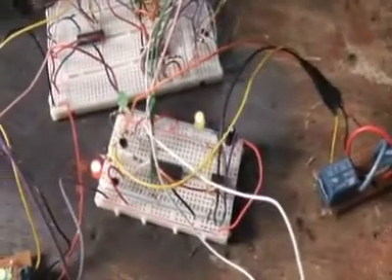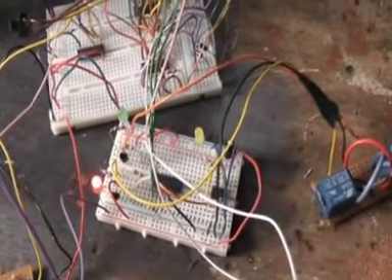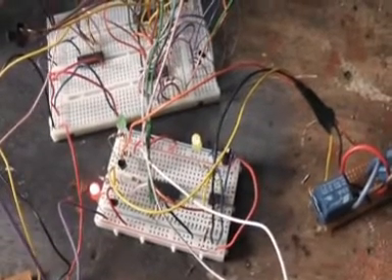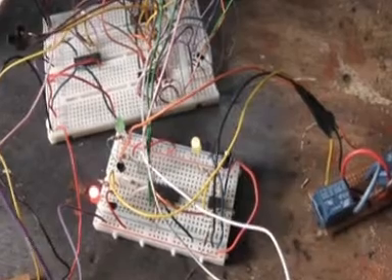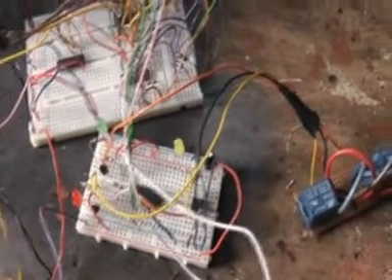The control circuits are 5 volts. The red LED is indicating the closing relay is energized, the flashing LED indicating no limits are made. When it hits the closed limit the red LED will go out, which has done.